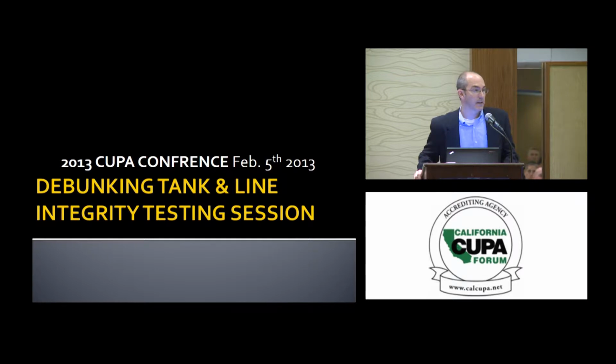The Sure Test methodology is a technology test that fits in this volumetric category. It's a magnetostrictive level sensor, which is the same technology used in a number of automatic tank gauge probes. It has integrated circuit temperature sensors, and it actually runs on a 9-volt battery. It is an underfill test method. It tests at the existing product level in the tank. The data is collected by the probe and then transferred into a laptop computer to actually run the calculation of the leak rate.